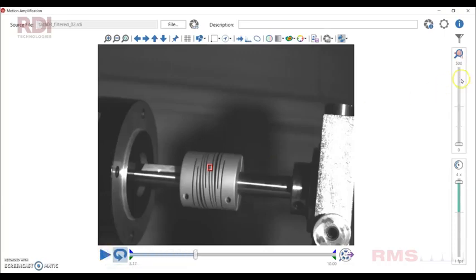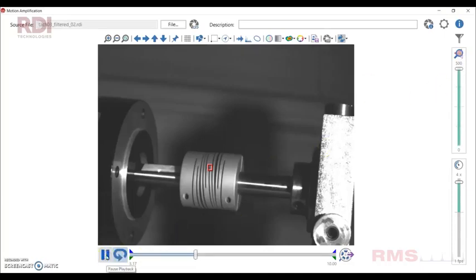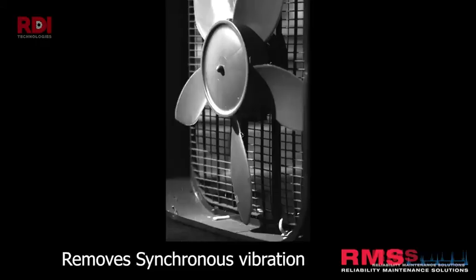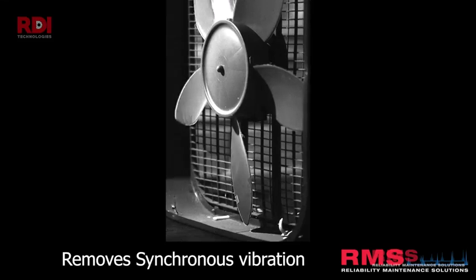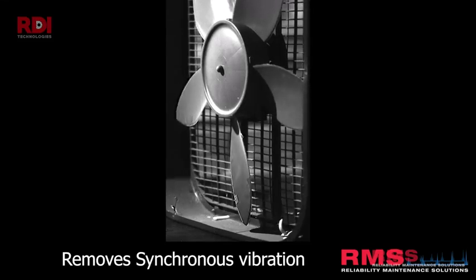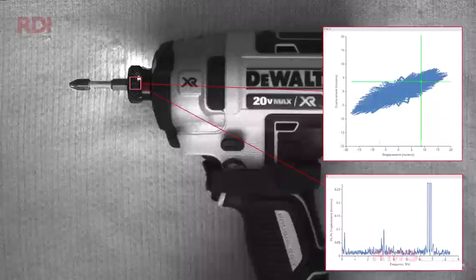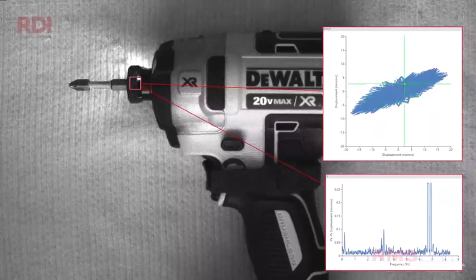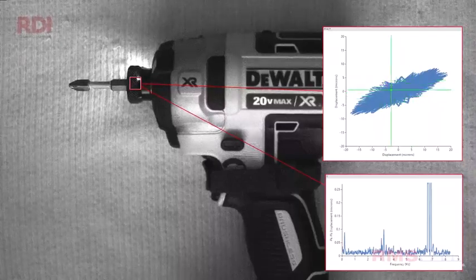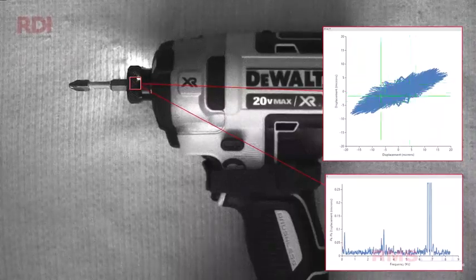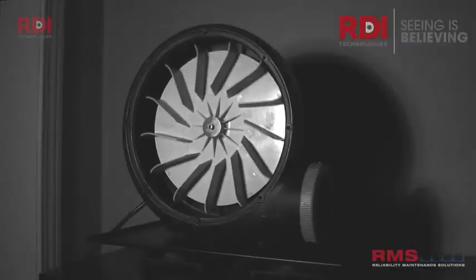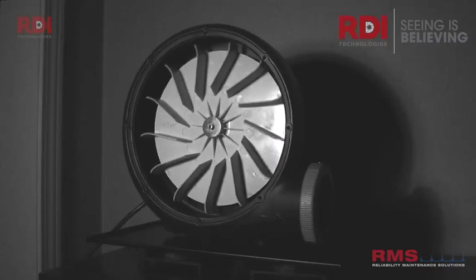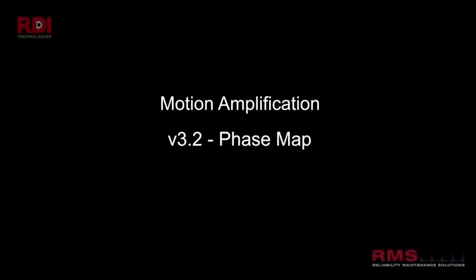Now here's a coupling. This is rotating. And what we're doing here, that's the standard video. We're going to amplify it now. And we can actually see the coupling flexing. So this is the non-synchronous frequencies we're looking at. It removes the one times. This is a fan impeller. We can see there's a little drill there. Absolutely amazing. I'm looking forward to getting some industrial shots for this. But truly amazing.